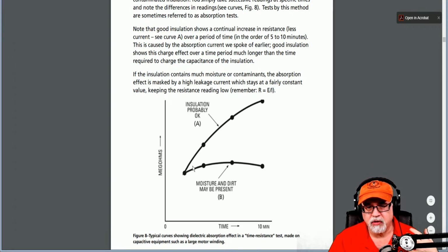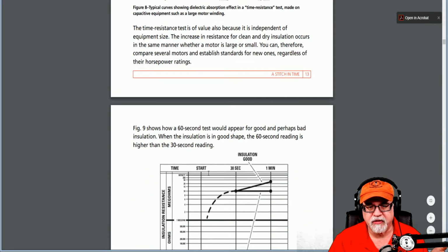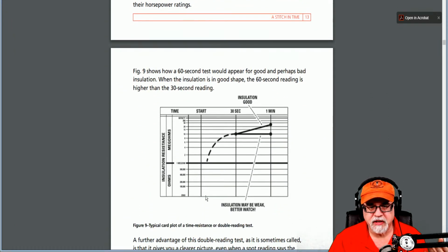So we're taking those values, okay? And I like to take a 1 minute, a 5 minute, and a 10-minute value, okay? A little more work, but a little more gives you a better picture. So as you can see here in a picture, those that are watching, you have another test that I'm telling you is the 60-second and 30-second. So watch the value at 30 and then take the value at 1 minute.